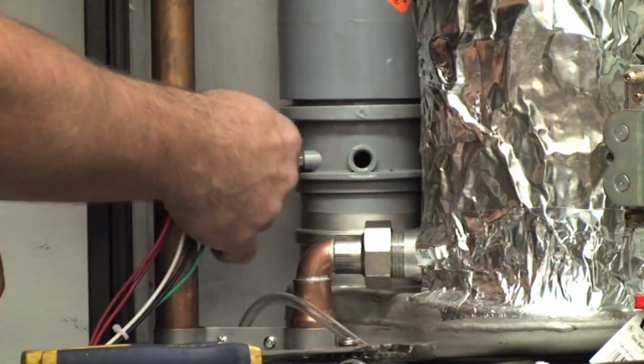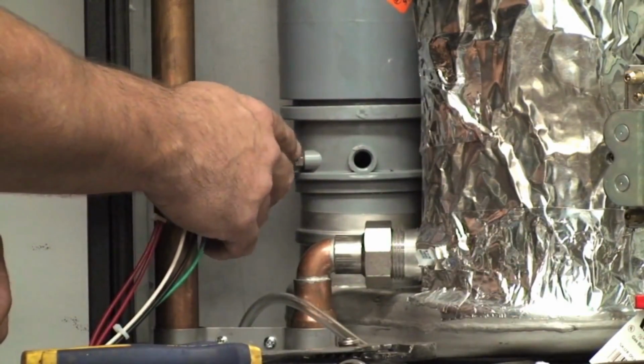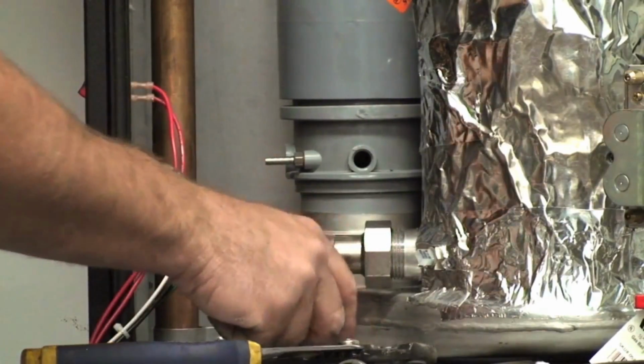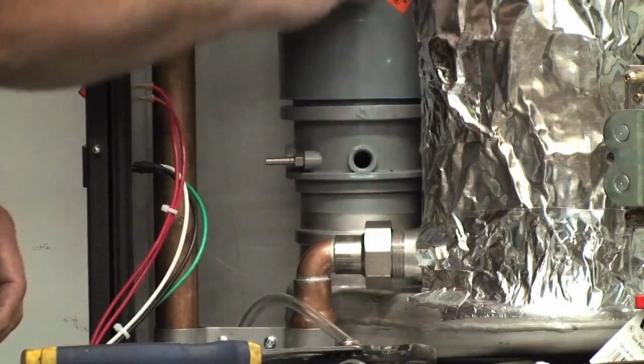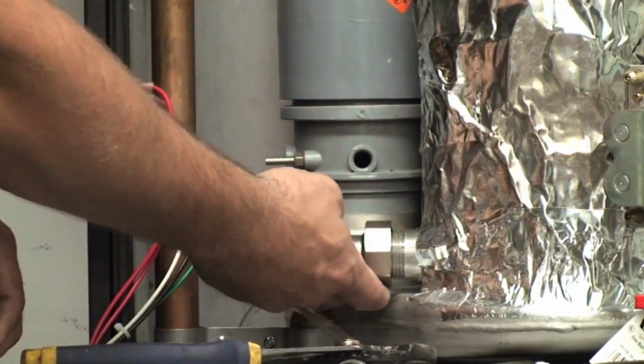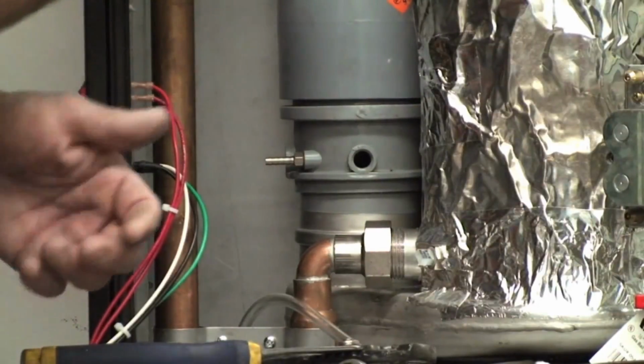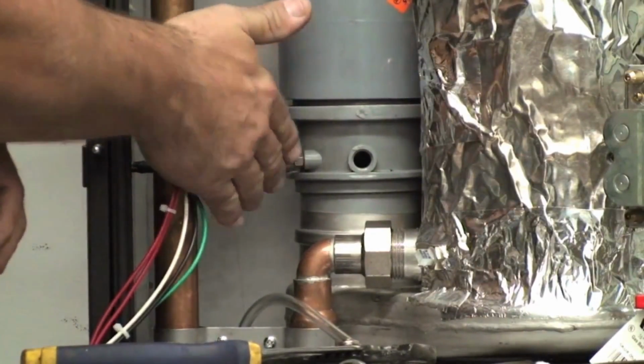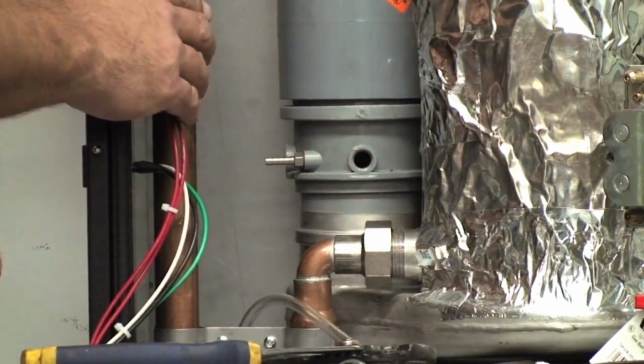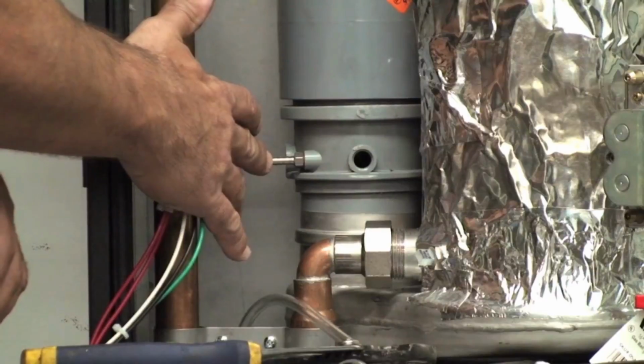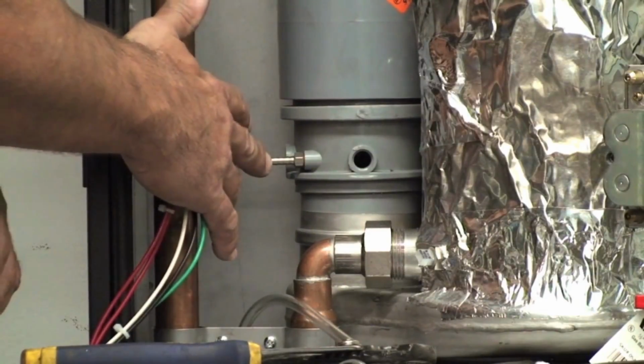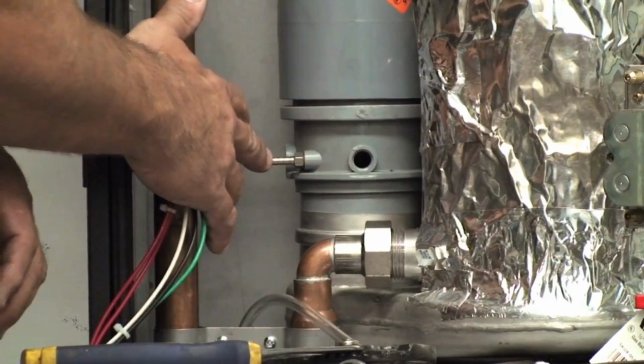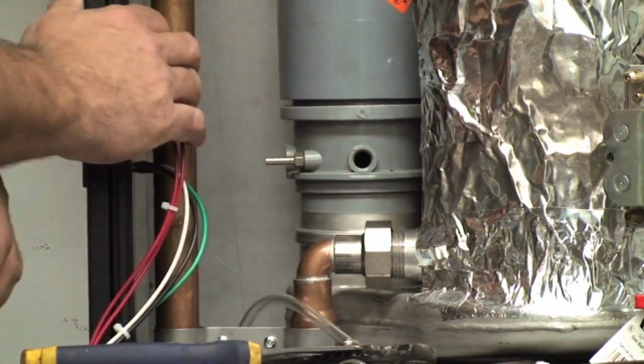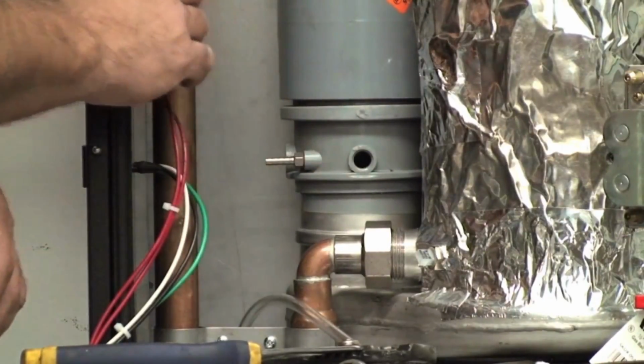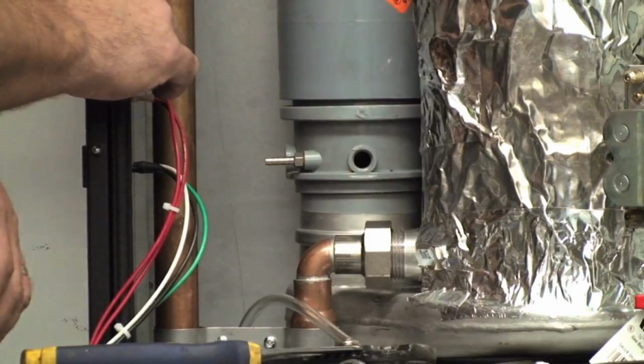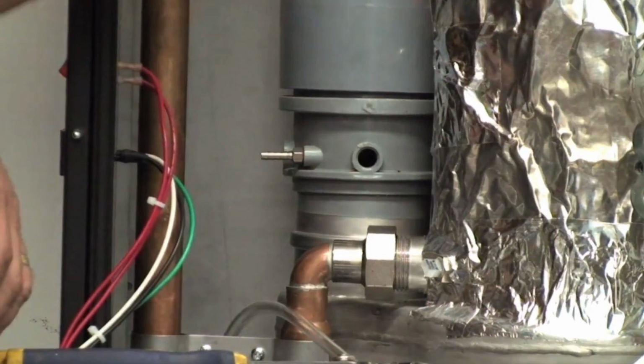This barb connection, which is made out of stainless steel and has a silicone O-ring, also is connected to our blocked vent switch. So we're monitoring the pressure from the outlet of the heat exchanger into the venting system. So if there's some downstream blockage, or anything's happening to the system, or even the check hangs up for whatever reason, we're going to measure it. The pressure switch is normally open, and then it closes on rise. So if the pressure gets too high in the vent system, the switch will become activated, and it will have to be addressed on the installation. It could be a blockage, snow, could be other things.